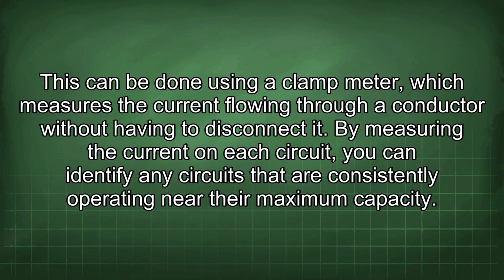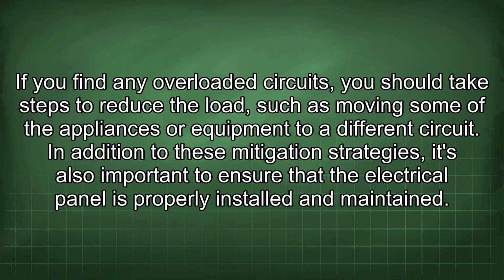By measuring the current on each circuit, you can identify any circuits that are consistently operating near their maximum capacity. If you find any overloaded circuits, you should take steps to reduce the load, such as moving some of the appliances or equipment to a different circuit. In addition to these mitigation strategies, it's also important to ensure that the electrical panel is properly installed and maintained.